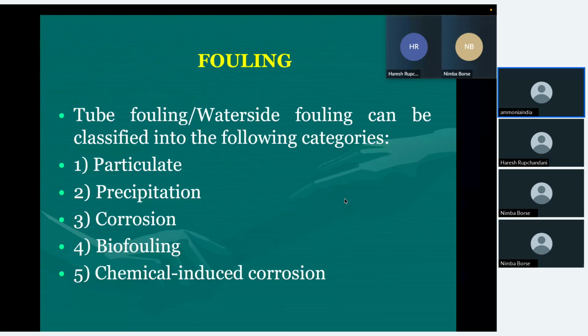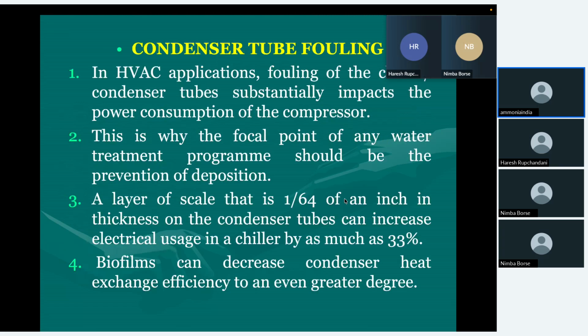The important subject is fouling. Many times people neglect this fouling of the tubes. Tube fouling, water side fouling, is disastrous, and it can be classified into the following categories. Particulate fouling is the actual mud or other undissolved solids, precipitation, corrosion because of the hardness of water, and biofouling, algae and other materials, and chemical induced corrosion. These are the 4 or 5 factors which contribute to fouling of the tubes. In HVAC applications, fouling of the condenser tubes substantially impacts the power consumption of the compressor. This is why the focal point of any water treatment program should be prevention of fouling.